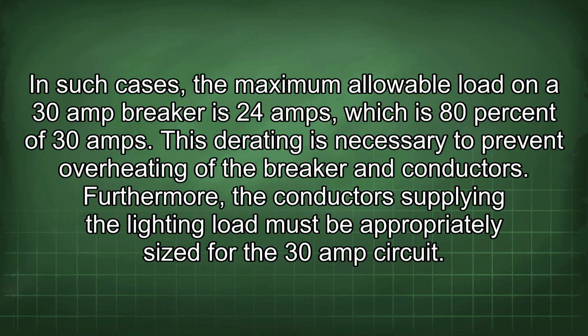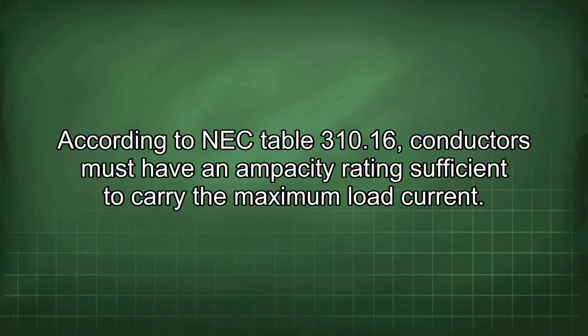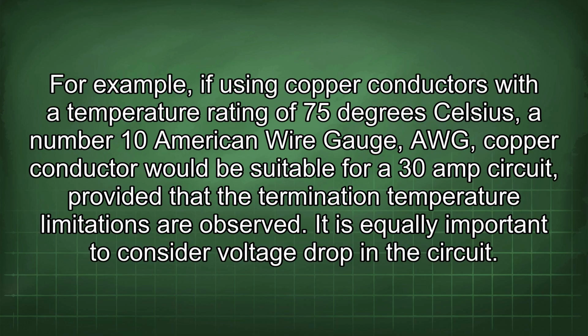Furthermore, the conductors supplying the lighting load must be appropriately sized for the 30 amp circuit. According to NEC Table 310.16, conductors must have an ampacity rating sufficient to carry the maximum load current. For example, if using copper conductors with a temperature rating of 75 degrees Celsius, a number 10 American wire gauge copper conductor would be suitable for a 30 amp circuit, provided that the termination temperature limitations are observed.